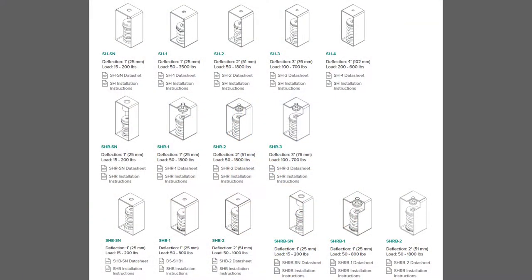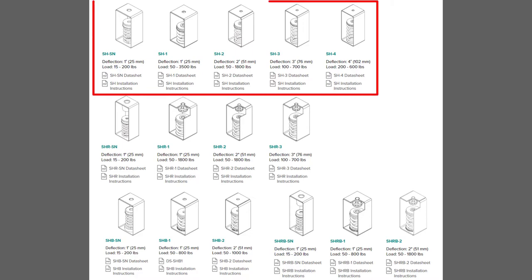Here is a compilation of images from our website showing four different variants of spring hanger isolators. At the top are the simplest versions. We call them SH for spring hanger. They come in four different sizes with four different deflections from one inch to four inch. The SH-SN and SH-1 both provide one inch deflection and the SH-3 and SH-4 boxes are the same size.